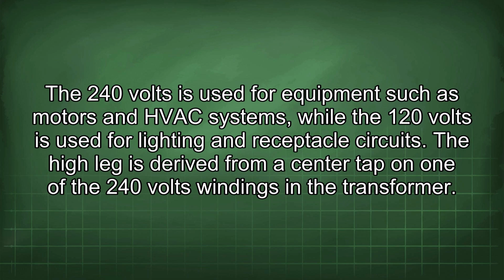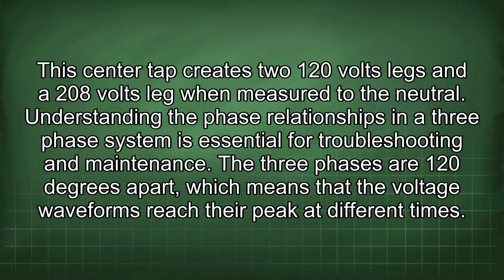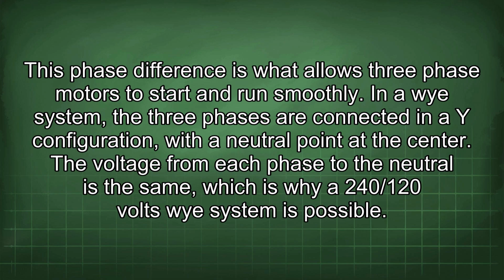lighting and receptacle circuits. The high leg is derived from a center tap on one of the 240 volts windings in the transformer. This center tap creates two 120 volts legs and a 208 volts leg when measured to the neutral. Understanding the phase relationships in a 3-phase system is essential for troubleshooting and maintenance. The 3 phases are 120 degrees apart, which means that the voltage waveforms reach their peak at different times. This phase difference is what allows 3-phase motors to start and run smoothly.